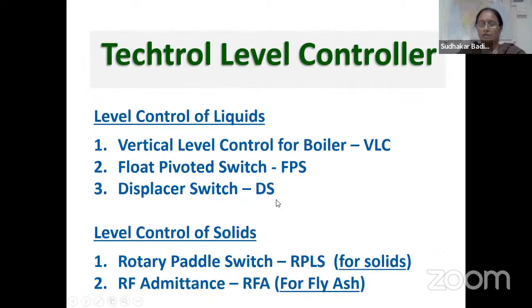Now, up till now, we have seen all the gauges which are based on glass type gauges or float type gauges. Now we'll see the switching part, or switch instruments. So these are the level control for liquids. The first one is a vertical level control for boiler, that is VLC. Then pivoted level switch, FPS. Then displacer level switch, DS.